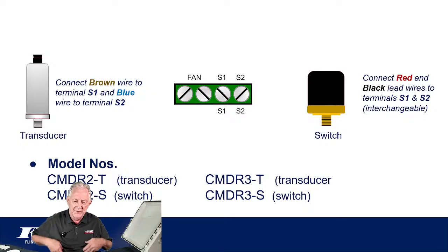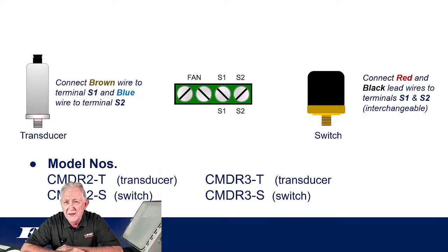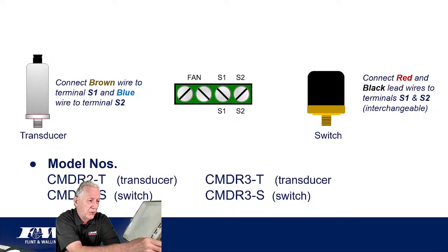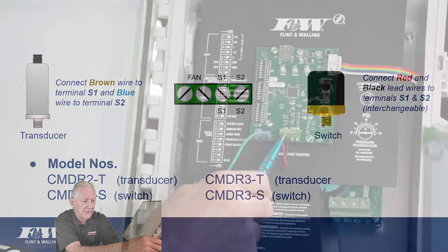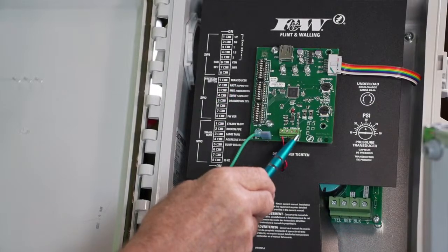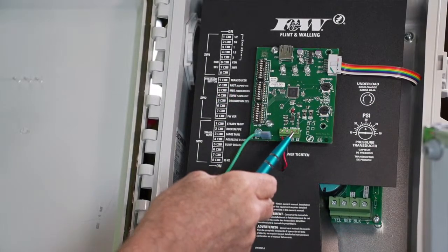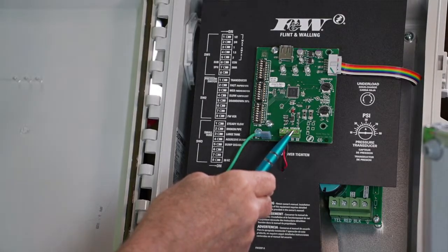The same thing with the Commander 3 drive, all right? So your suffix is going to depend on whether you want that drive shipped with the switch or with the pressure transducer. Now, when we were into this drive, and I showed you this middle port here, I said that 2 of those 4 run down to the fan, and it left us these other 2 for whatever device we're going to use to turn this drive on and off.